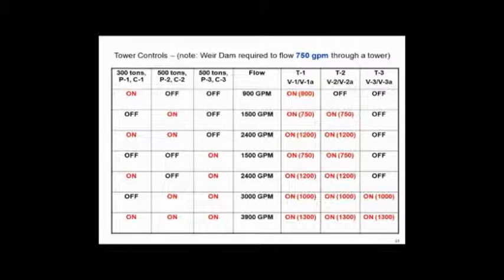Let's start off with a wintertime operation. The little 300 ton chiller's on line. So P1's on, C1's on. P2, chiller 2, chiller 2 is off. Same thing for 3, it's off. So what is the flow rate going out to my towers? 900 GPM. Great. I've got 900 GPM going to my towers.